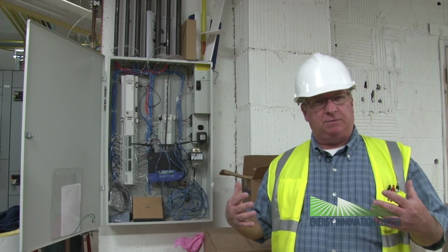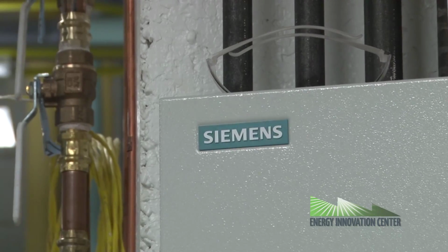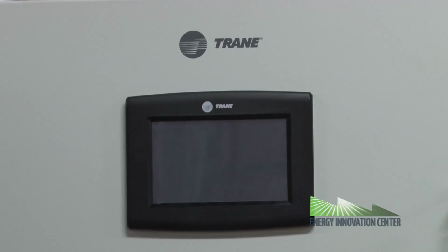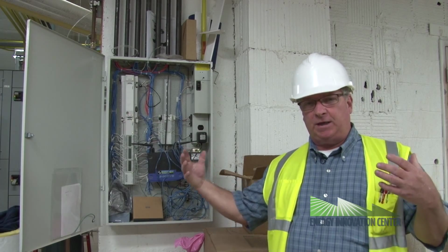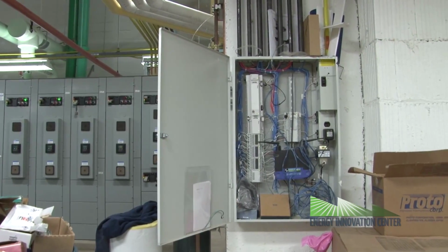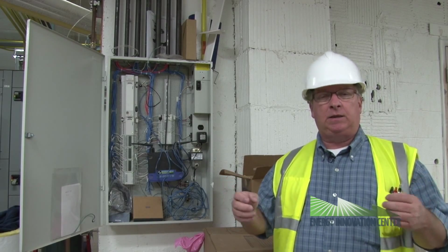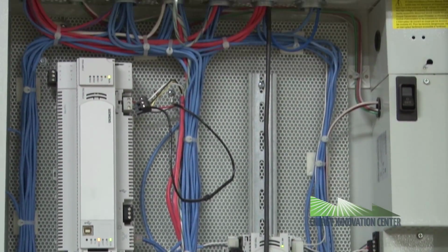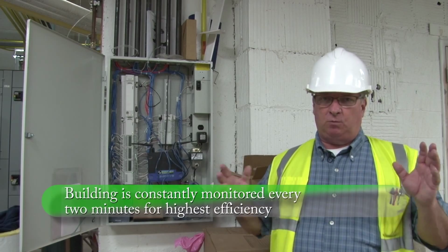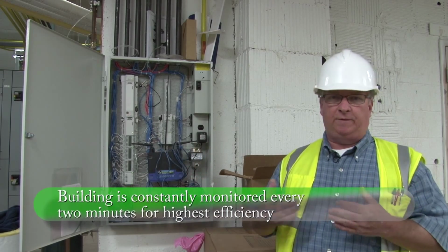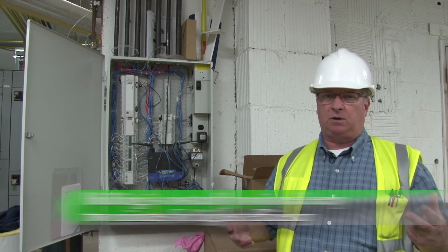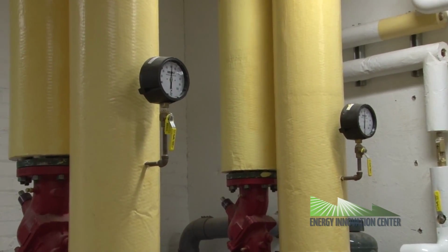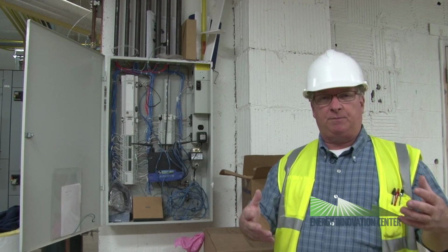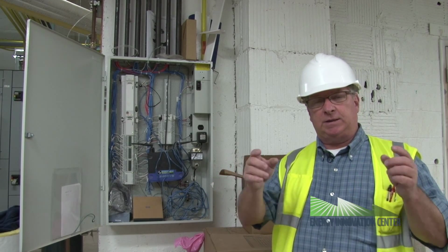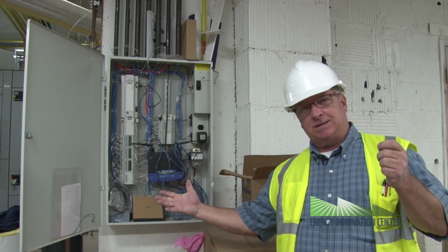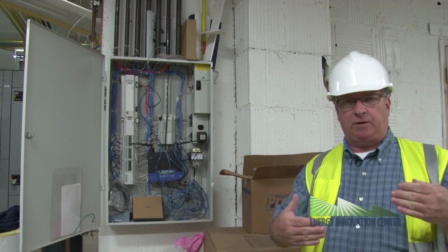As I mentioned before, we have 7 systems integrated into one. We've had a lot of interest from Siemens and Eaton and Trane to bring in their service techs to see exactly how they integrate systems and how we've done it on this project. Our building integration system is running on its own fiber VLAN, which keeps other building traffic off the data network, which would cause a slowdown of the transmission of the values. So we've designed in a VLAN just for data, and we're moving at such a fast pace. Every 2 minutes, there's a lot of data that we're collecting. We're going to have a true virtual automation system of the operating building. They can change values, they can mix values up and see what the response is. And the way we do that is as they change a value, we go back in historical data and see exactly what values were at that time, and we populate the graphic with that accordingly.